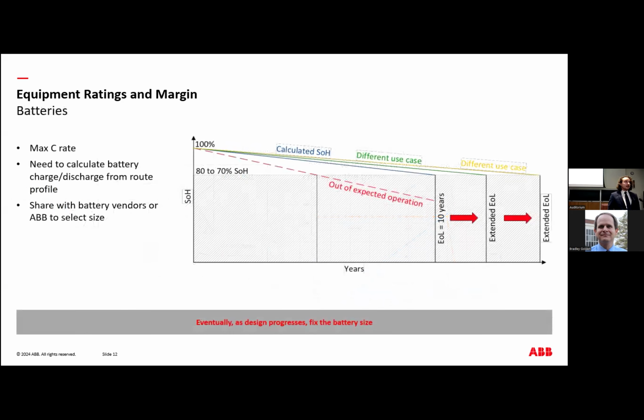Onto the batteries. Batteries are sized by the route profile, the maximum C rate, which is how fast you need to charge or discharge the battery, so the maximum power that you need, and then the lifetime. And the lifetime is calculated typically by ABB or another integrator or the battery vendor because it's pretty proprietary. But you can see, the green line here, or the blue line, is the calculated state of health. So if you want a 10-year life, this is how much energy you can provide on each cycle. And if you build this vessel and you put it into service and somebody says, oh, we need to go a little faster, and you use more power, the battery will not last 10 years, right? But if you use less, the batteries will last longer.